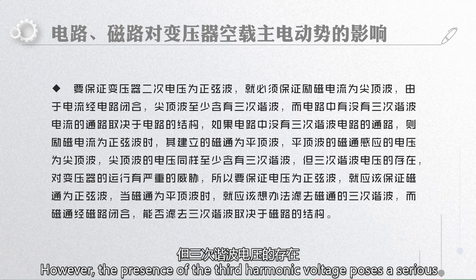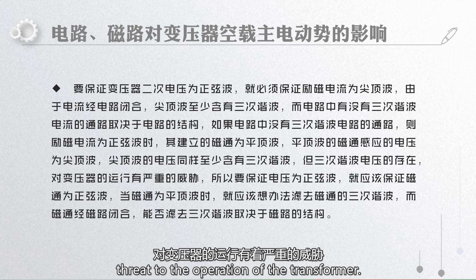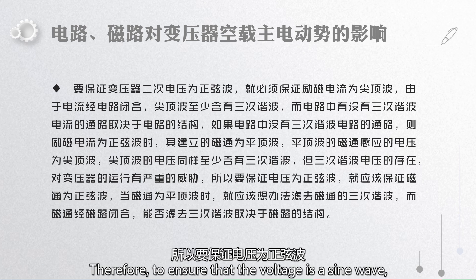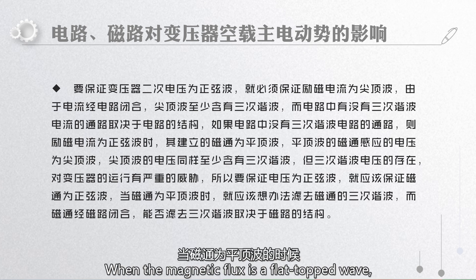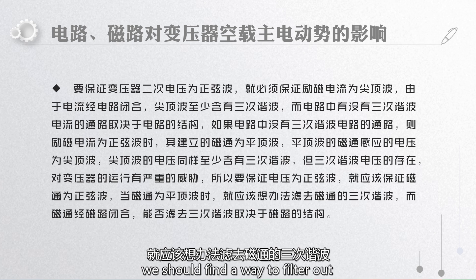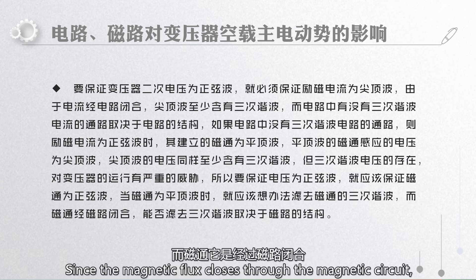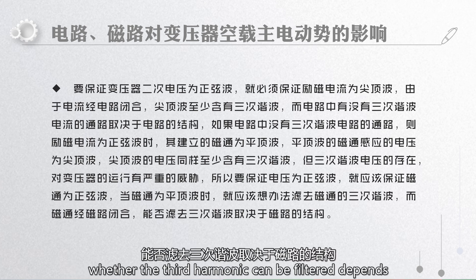The peaked wave voltage also contains at least the third harmonic. However, the presence of the third harmonic voltage poses a serious threat to the operation of the transformer. Therefore, to ensure that the voltage is a sine wave, the magnetic flux should be a sine wave. When the magnetic flux is a flat-topped wave, we should find a way to filter out the third harmonic of the magnetic flux. Since the magnetic flux closes through the magnetic circuit, whether the third harmonic can be filtered depends on the structure of the magnetic circuit.